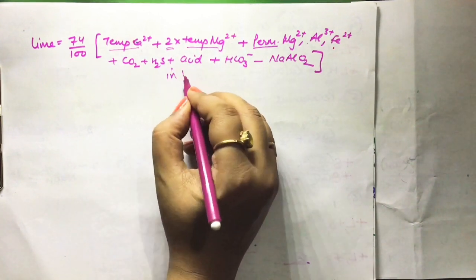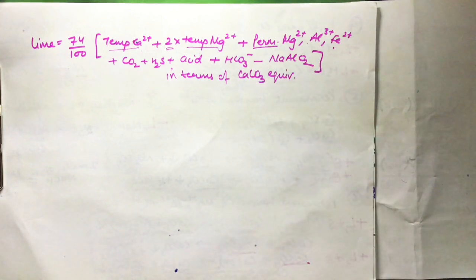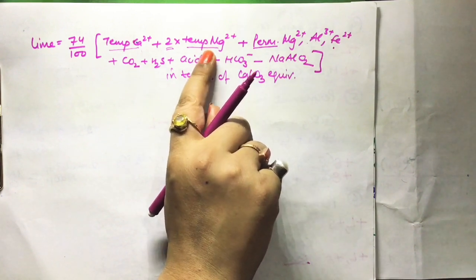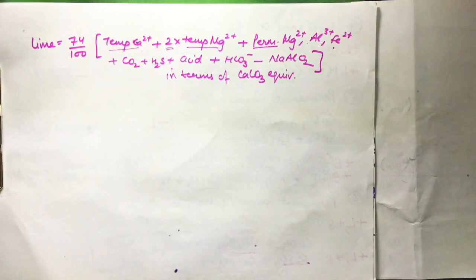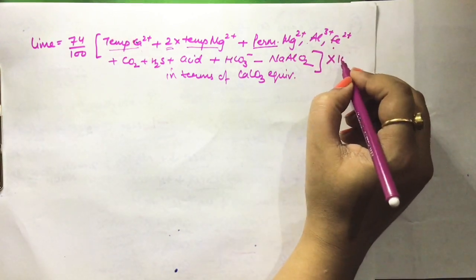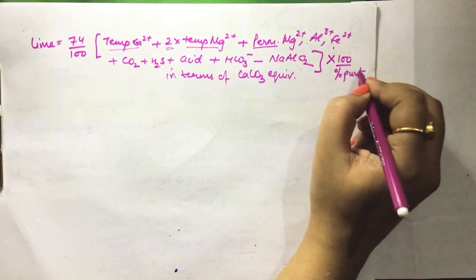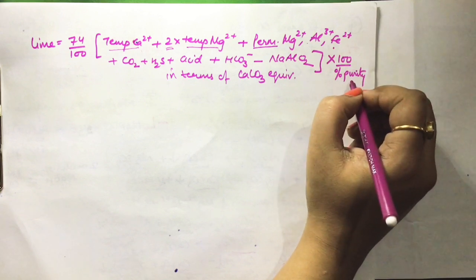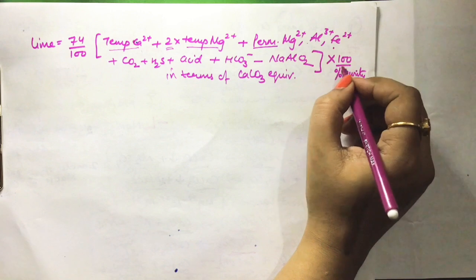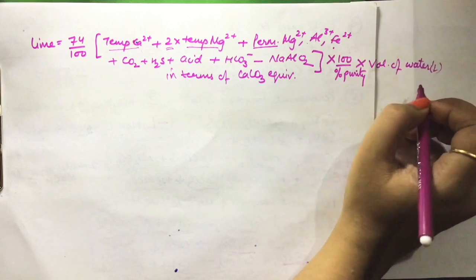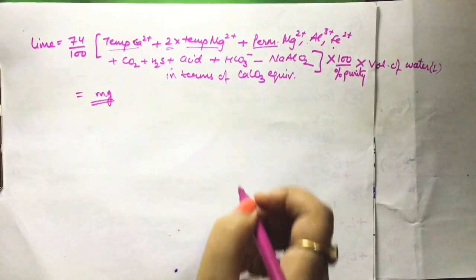These impurities are given in water in terms of calcium carbonate equivalent, so we will convert these impurities to calcium carbonate equivalent and put them in the expression. The value 74 is the molar mass of lime. We then multiply this expression by 100 divided by percentage purity, and multiply by volume of water in liters. The answer will come in mg.